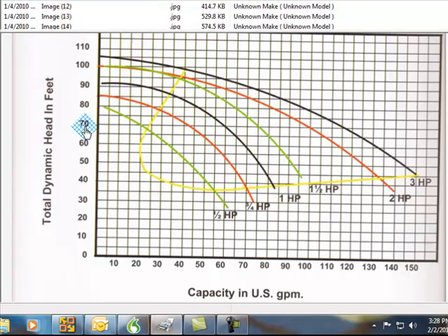You can calculate your head, what your system does now. With your sand filter, your filter being clean, and everything being ideal, you put a vacuum gauge on your pump and you put a pressure gauge on your pump, and you can calculate what your total head is. So, we can get into that. If you guys want to talk about that, we can start doing education classes. But I wanted to start talking about this. It's not, and I hear it all the time. I can't express it enough. I got it basically on the ground, so it's zero worth of head. I am capable of all the water in the world. I can half-horsepower pump, I can do almost 80 gallons a minute. No. Everything has to be calculated.